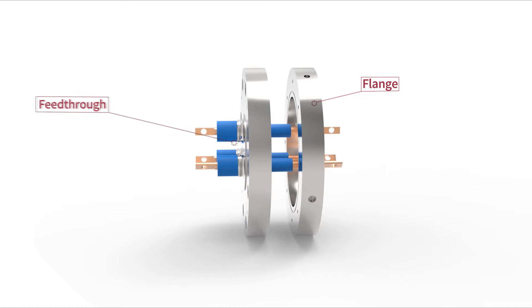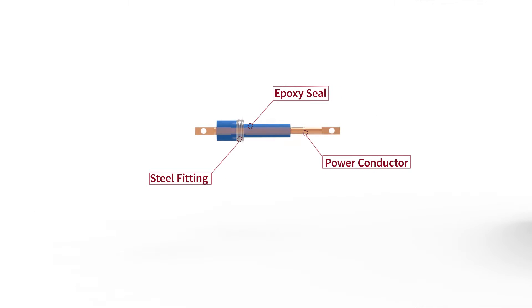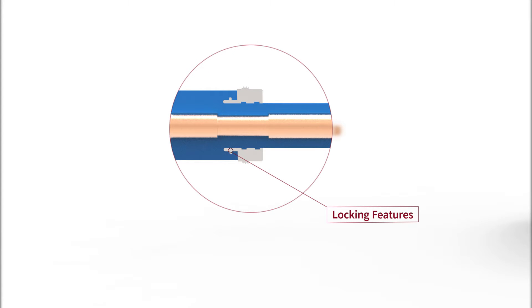The breakthrough behind this new technology is that we use the thermal expansion mismatch between epoxy and metals to our advantage. The shrink of epoxy improves the bond strength to both the fitting and the copper conductors.